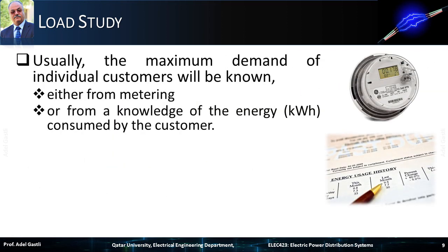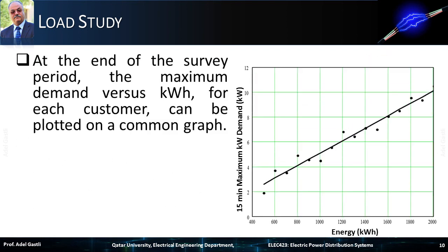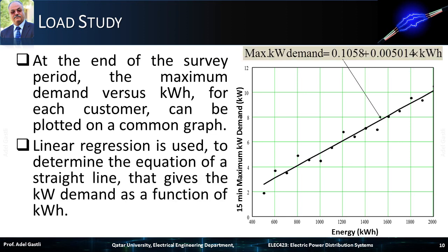Usually the maximum demand of individual customers will be known, either from metering or from a knowledge of the energy consumed by the customer. Some utility companies will perform a load survey of similar customers in order to determine the relationship between the energy consumption in kilowatt-hours and the maximum kilowatt demand. At the end of the survey period, the maximum demand versus kilowatt-hour for each customer can be plotted on a common graph. Linear regression is used to determine the equation of a straight line that gives the kilowatt demand as a function of kilowatt-hour.